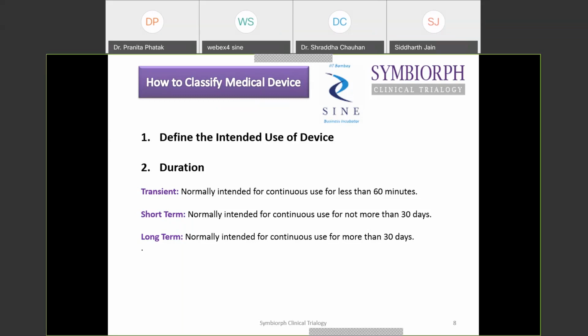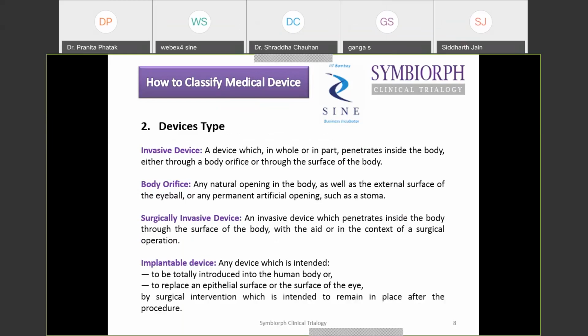After you have done these two steps, the third step is to define the type of device it is, whether it is an invasive device, a body orifice device, a surgically invasive device, an implantable device, or an active medical device or active diagnostic device. So you have to define which category your device falls into. Why it is very important to define the type of device, I will let you know when we discuss the implementing rules to classify. Suppose your device falls under body orifice, meaning any natural opening in the body, as well as the external surface of the eyeball, or any permanent artificial opening such as a stoma. You can classify it as a body orifice device if it is used in a body orifice.